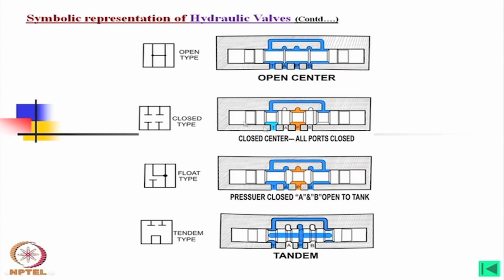This means that when we need very quick action and intermediate position of the load, we shall go for closed type, whereas if we think of saving the energy, we will go for open type, fully open type, but in most cases you will find tandem type might be the best one for common applications.